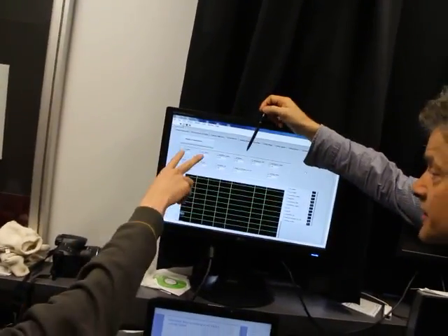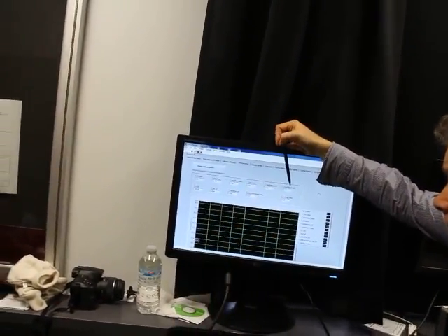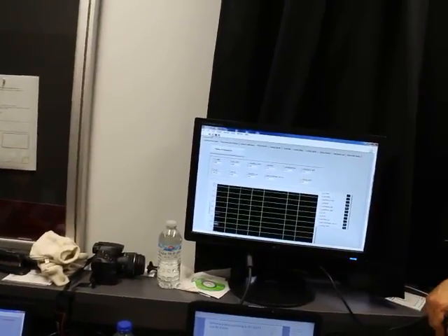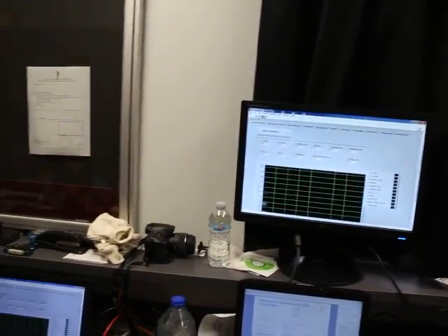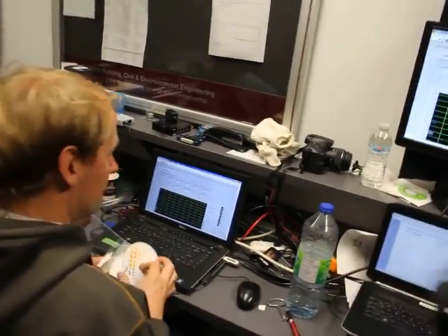T in air, that's ventilation. That one is warmer. Where's T in air? Inlet air. We don't have inlet air, because that's not connected. What we have is ambient, and we have the two in the ventilation unit. Then how does it calculate the inlet air amplitude if it doesn't have it? It considers the ambient temperature.